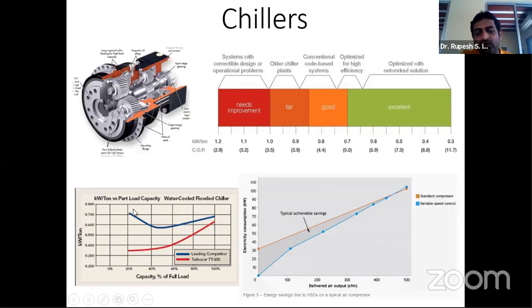So if you look at the blue line, this shows the classic centrifugal type of chiller, and the kilowatt per ton varies somewhere between 0.6 and 0.7 from part load to full load. But with magnetic levitation chillers coming in, we can achieve part loads of almost 0.3 to 0.4 kilowatt per ton. So that itself gives almost a 100% improvement at a particular part load efficiency from an existing chiller to the next generation kind of chiller.